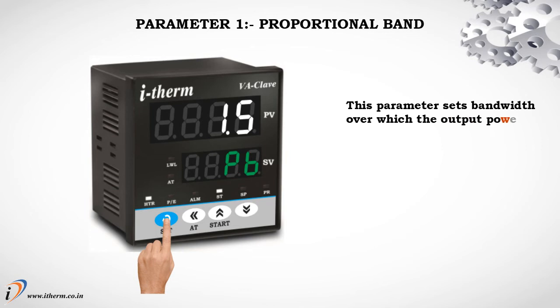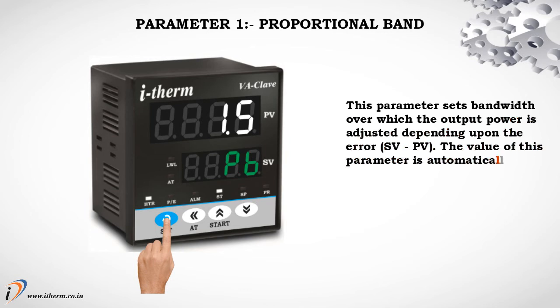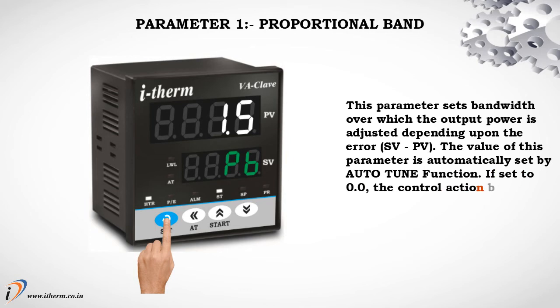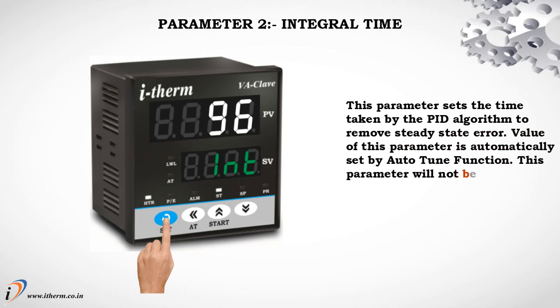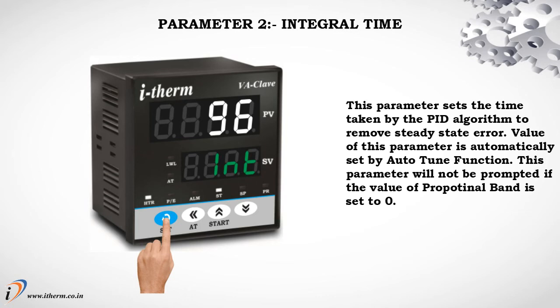Parameter 1: Proportional Band. This parameter sets the bandwidth over which the output power is adjusted depending upon the error. The value of this parameter is automatically set by the auto tune function. If set to 0.0, the control action becomes on/off. Parameter 2: Integral Time. This parameter sets the time taken by the PID algorithm to remove steady state error. The value of this parameter is automatically set by the auto tune function. This parameter will not be prompted if the value of proportional band is set to 0.